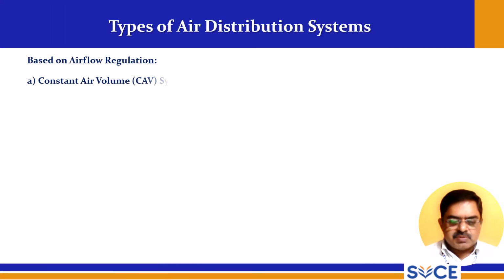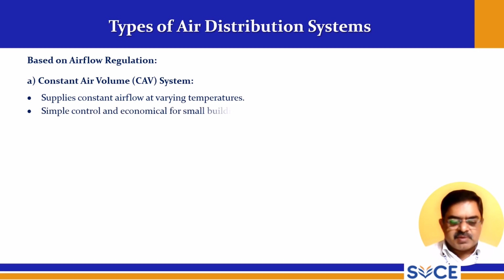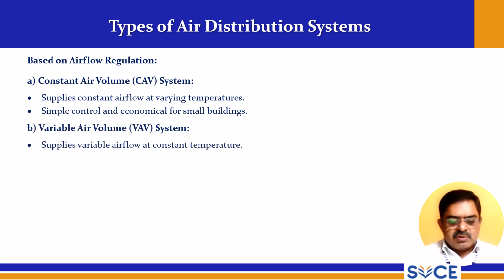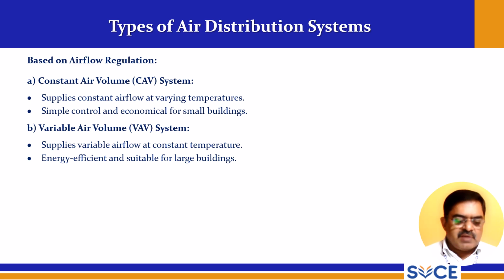So, types of air distribution systems based on airflow regulation. Constant air volume (CAV) system supplies constant airflow at varying temperatures; it has simple control and is economical for small buildings. Variable air volume (VAV) system supplies variable airflow at constant temperature; it is energy efficient and suitable for large buildings. So VAV systems are very much suitable for large buildings.